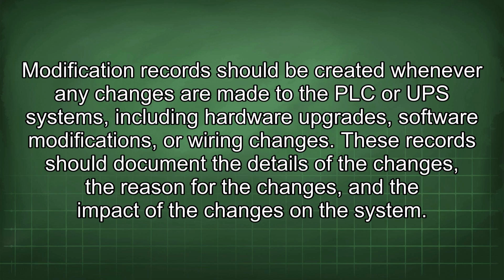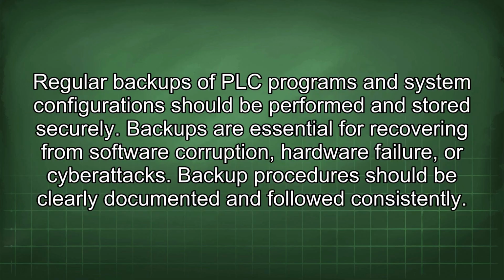Modification records should be created whenever any changes are made to the PLC or UPS systems, including hardware upgrades, software modifications, or wiring changes. These records should document the details of the changes, the reason for the changes, and the impact of the changes on the system. Regular backups of PLC programs and system configurations should be performed and stored securely. Backups are essential for recovering from software corruption, hardware failure, or cyber attacks. Backup procedures should be clearly documented and followed consistently.